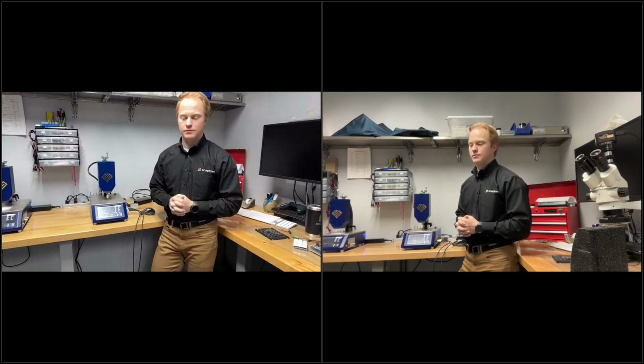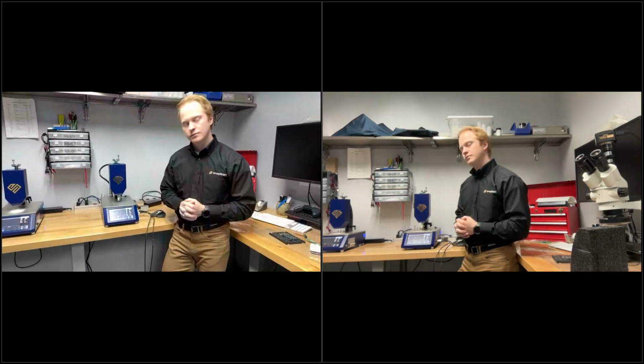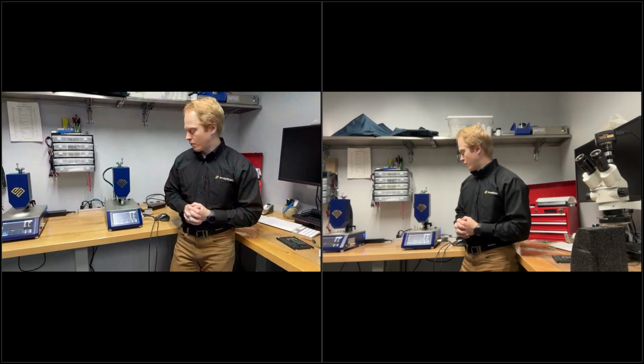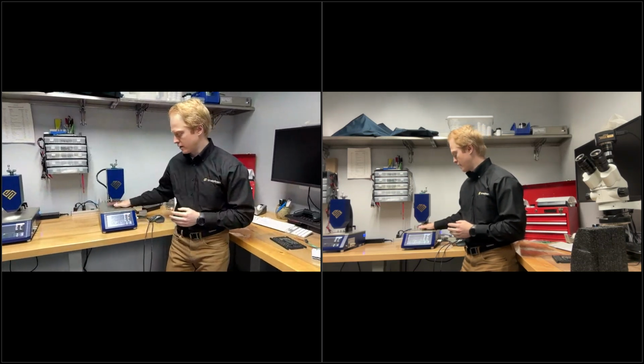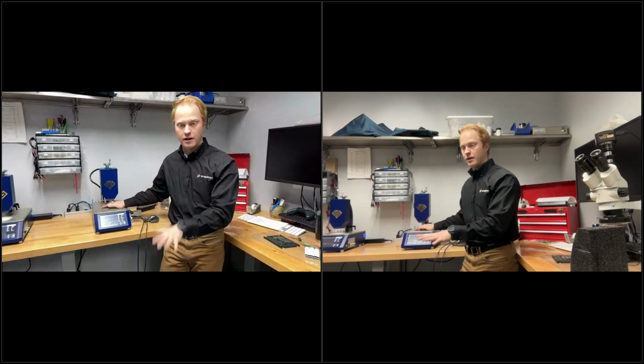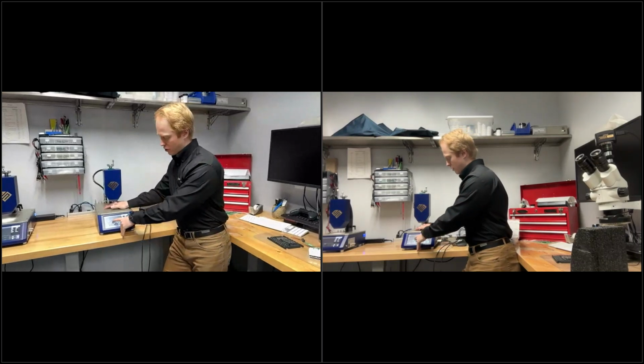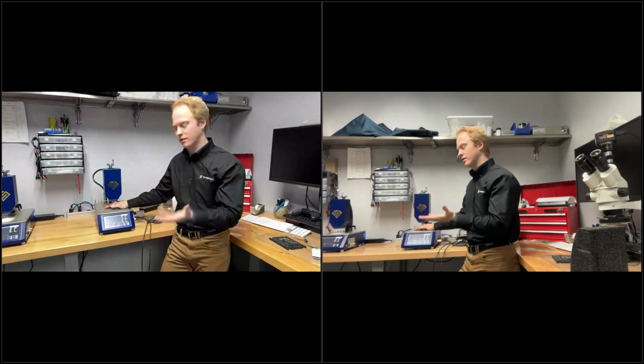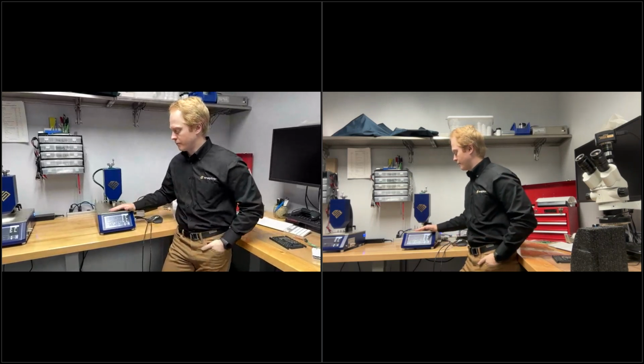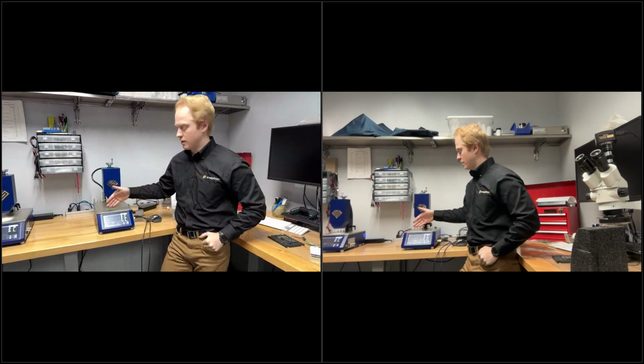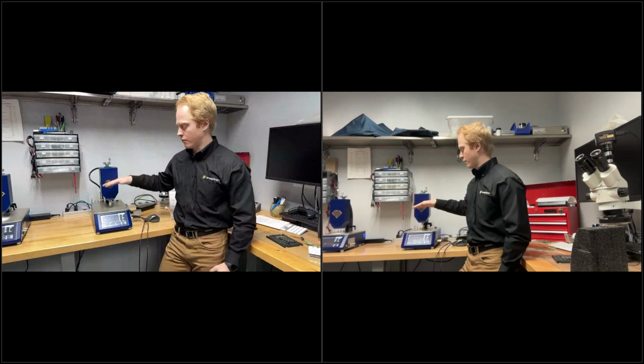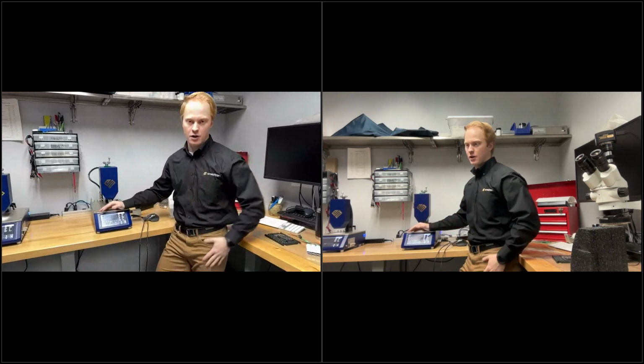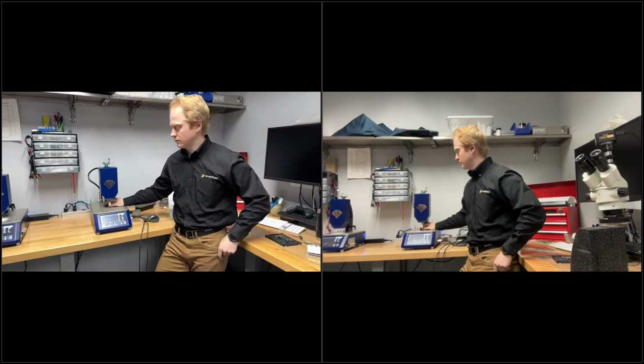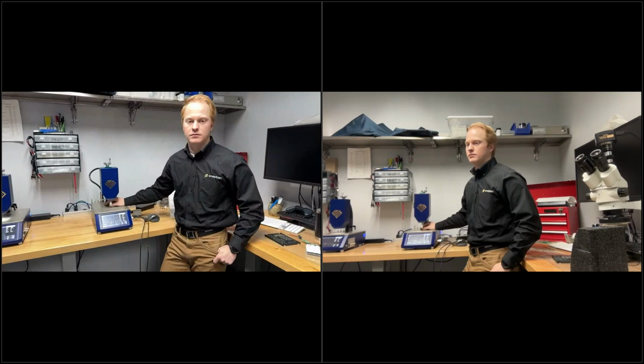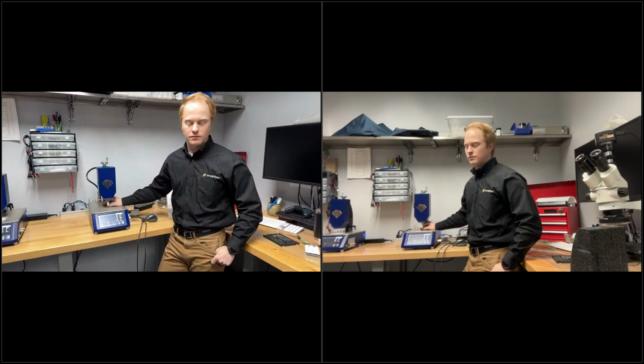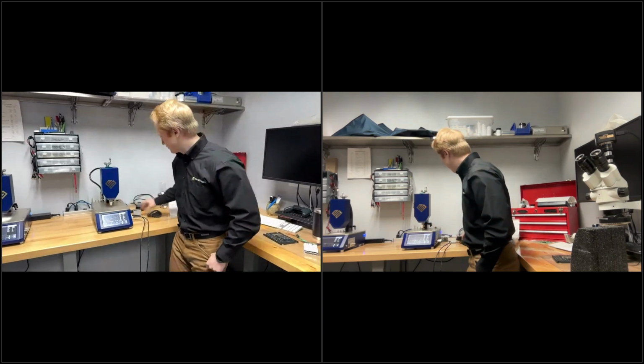Does the device detect local peaks when the dome starts to invert? So for inversion testing, it will let you know that the dome has gone bistable and has not returned, because the return curve will not generate since there's nothing pushing back on the force tip here. So in essence, yes, and then it will let you know the absolute force max throughout that force displacement curve before it goes bistable. So I hope that answers your question. Rita, if that doesn't answer your question, just let us know. We can either meet up after.